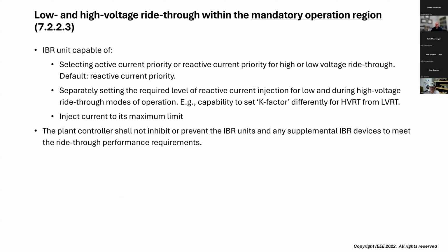The first set of capabilities to consider when the IBR is in the mandatory operating region, and this applies at the IBR unit level or the point of connection, is that the units need the ability to operate in either an active current or reactive current priority mode. And they need to be able to do either mode for either high or low voltage ride through. By default, the standard says reactive current priority. Additionally, we need to be able to set the level of reactive current injection per unit voltage deviation differently for low voltage and high voltage ride through modes.